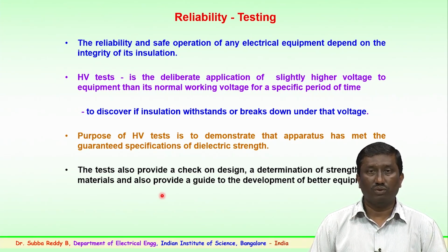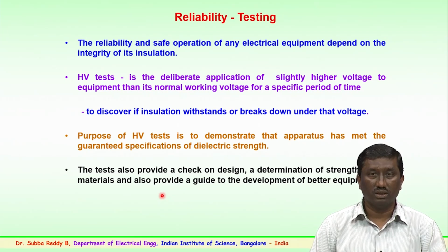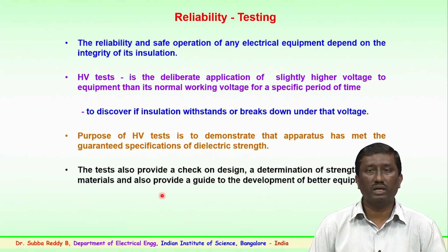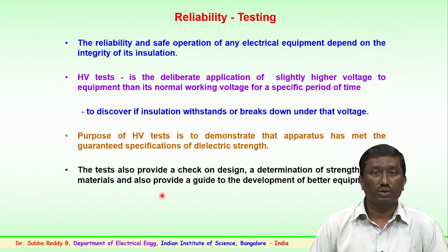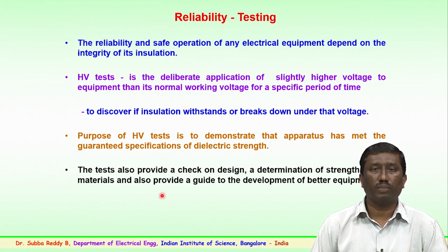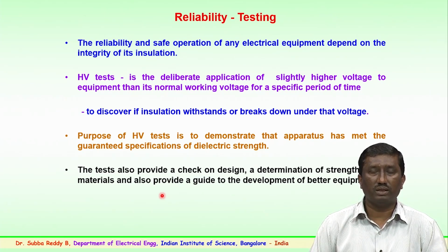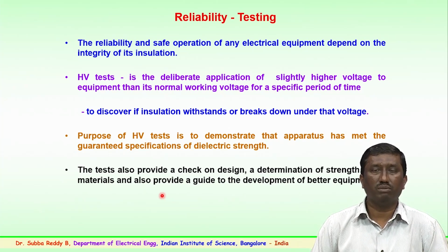This is how the high voltage tests are conducted in the industries, that is the manufacturing units, as well as the research laboratories or the certification laboratories. So, a voltage intentionally slightly higher than the equipment sees in the field is applied for a specific period of time and its integrity is verified. It also helps to discover whether the insulation withstands for a period or breaks down under that voltage. So, this gives an idea of how reliable the product is for use in the field.